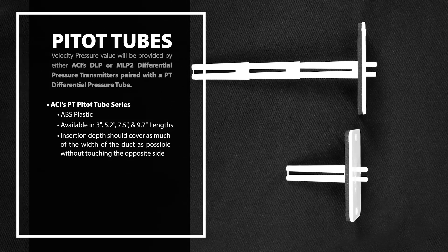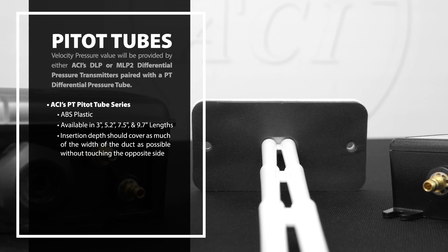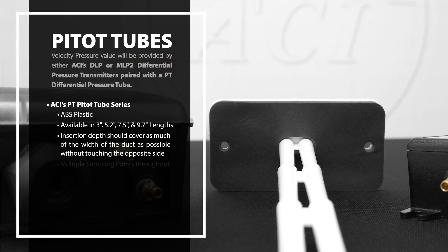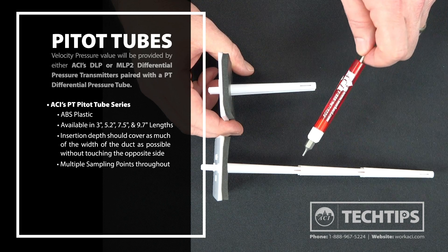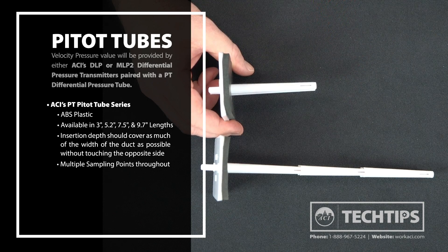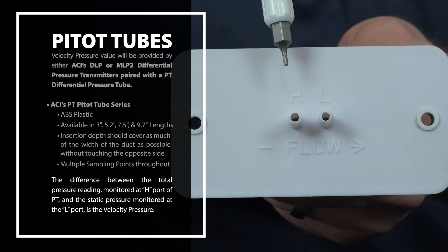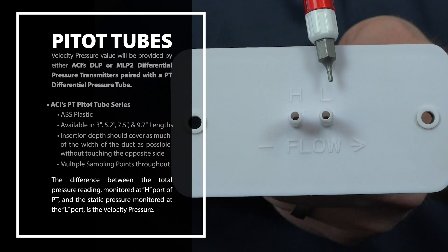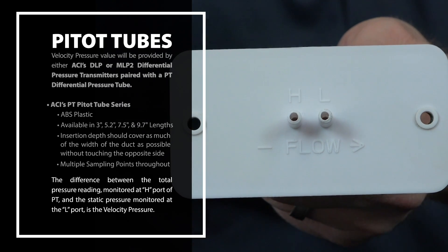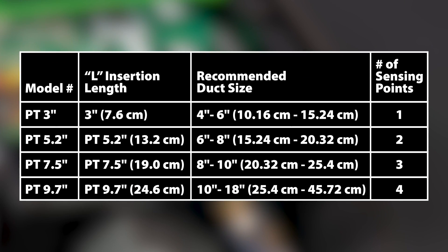The insertion depth should cover as much of the width of the duct as possible without touching the other side. There are multiple sampling points throughout the span of the PT, with the number of sampling points depending on the length of the PT. The difference between the total pressure reading monitored at the H port of the PT and the static pressure monitored at the L port is the velocity pressure. Here is a table showing our recommended insertion lengths by duct size.